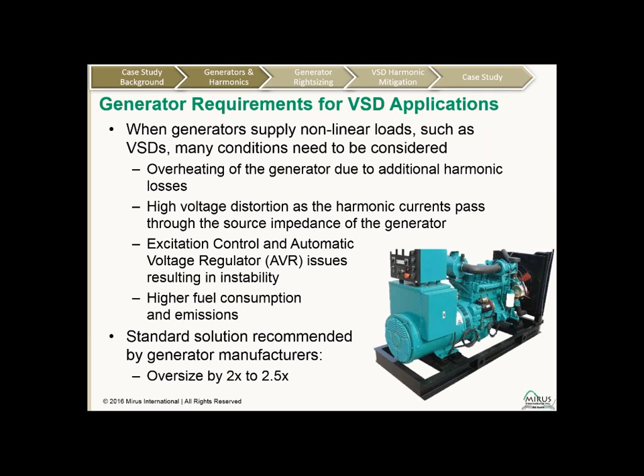So generators, when they're supplying variable speed drives, will create higher losses in the generator and cause overheating of the generator. The higher impedance of the generator will result in higher levels of voltage distortion as the harmonic currents pass through that generator impedance. The high distortion levels can cause excitation control and automatic voltage regulator, or AVR, issues, resulting in instability of the generator. And the heavier losses will introduce additional fuel consumption, and with that extra fuel consumption are added emissions into the environment. And the standard solution recommended by generator manufacturers is to oversize the generator by 2 or 2.5 times the load.